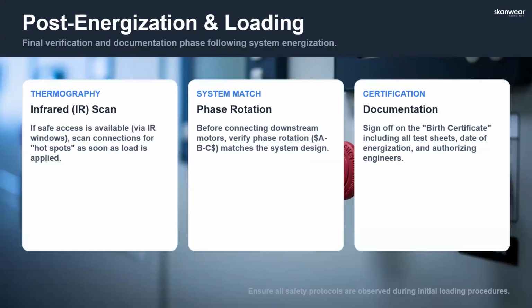And then obviously our post-energization. Now we've done our switching, we've energized the system. Some of us do IR scanning, where we're going in and checking for hot spots and verifying that everything looks good. Phase rotation, making sure that we're seeing the right rotation and that we have the proper voltages. And then lastly, but not least, we're going to document, which some call a birth certificate, signing off that the equipment is new and energized and has gone through all the processes, identifying the dates of the energization and who were the engineers during that.